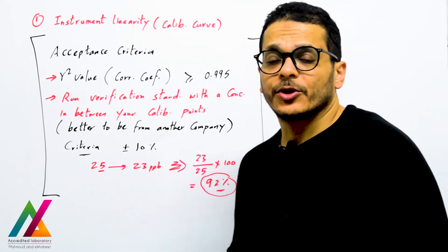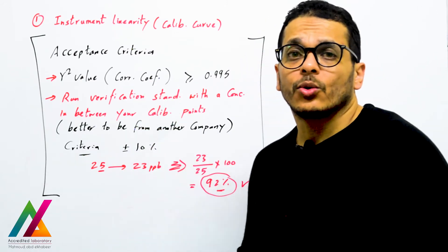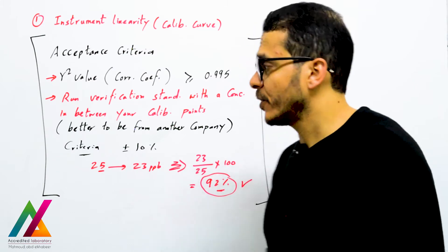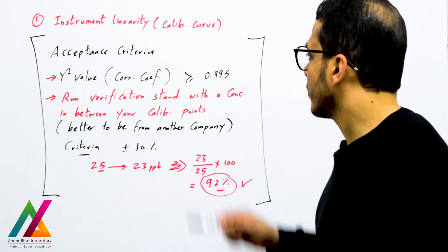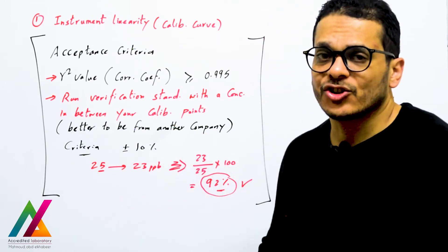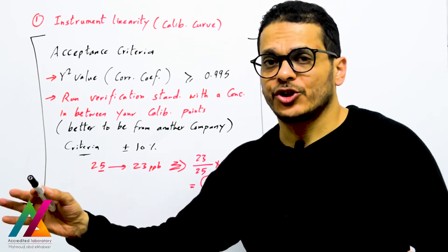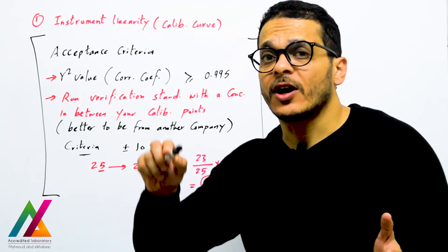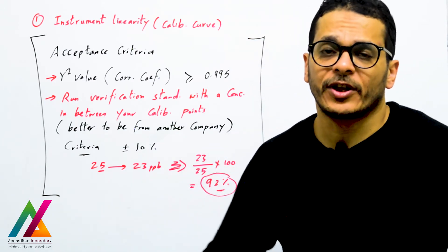The acceptance criteria for the calibration curve include first the R-squared value, or correlation coefficient, which represents the linearity of your calibration curve. It should be higher than or equal to 0.995 according to most guidelines, and sometimes higher than or equal to 0.99. You should also run a verification standard with a concentration between your calibration points — for example, 25 ppb if your calibration range is 1 to 100 ppb.